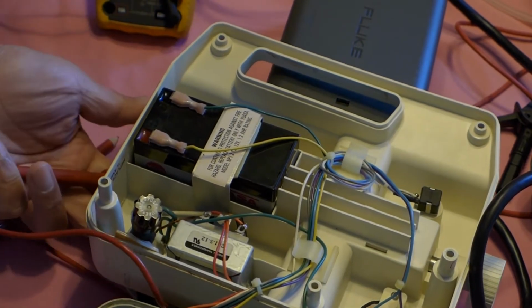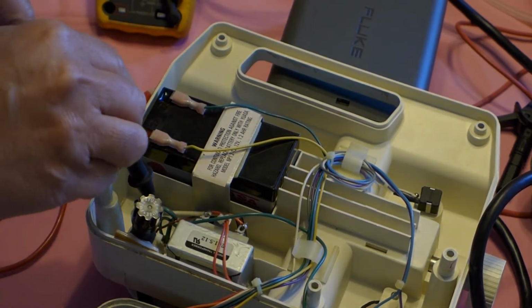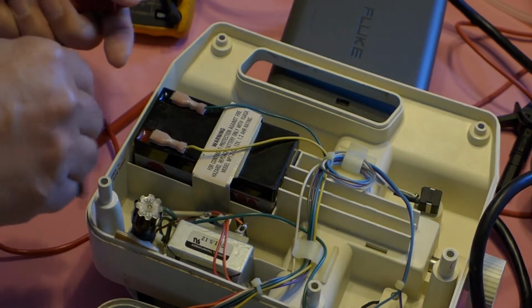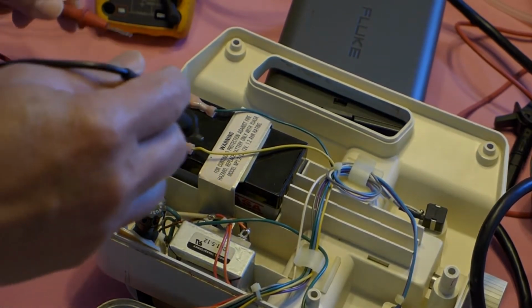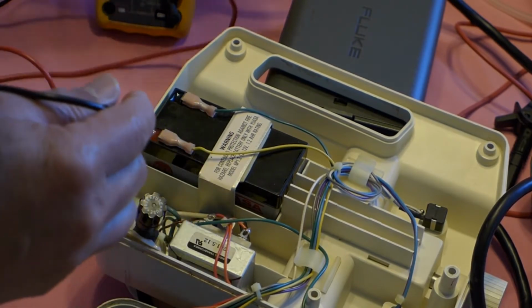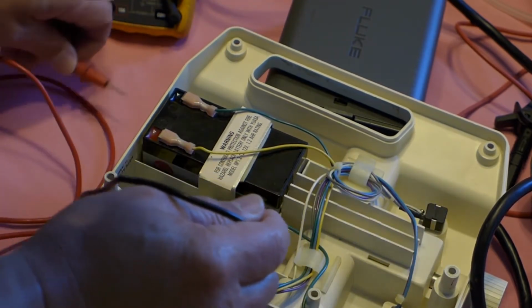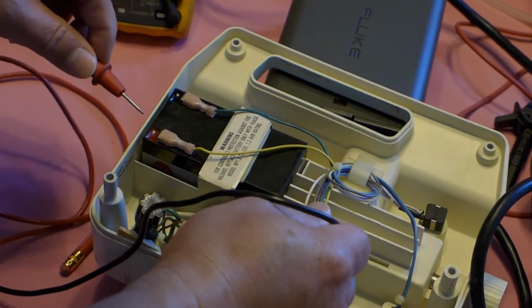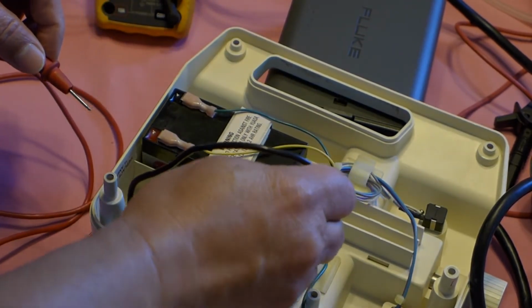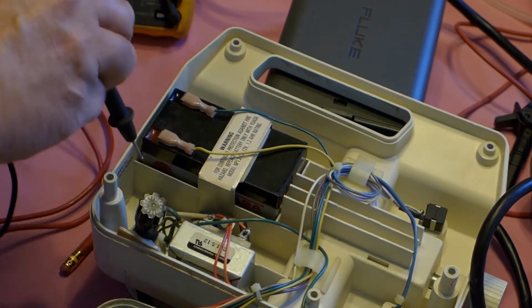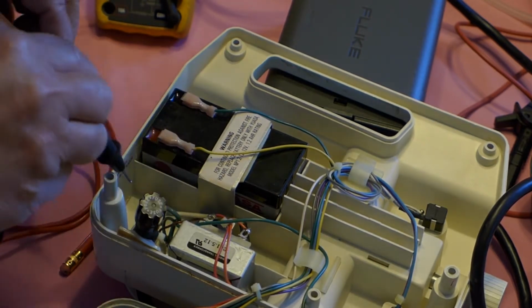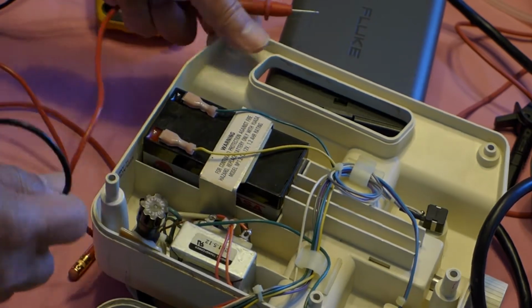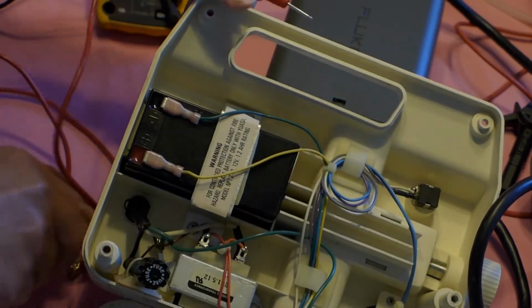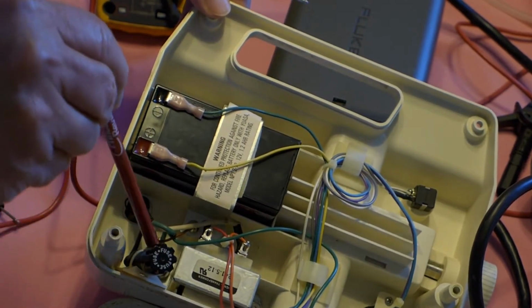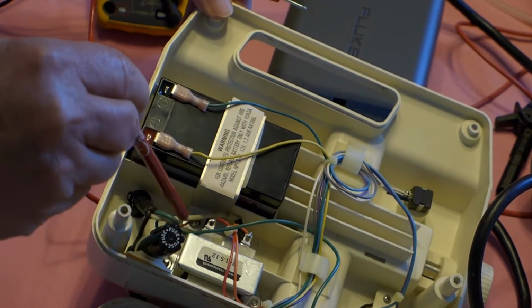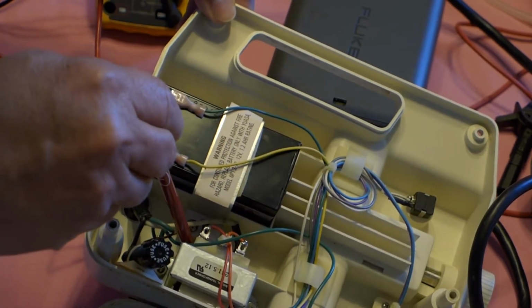So in the back, when you flip that, you need to check the leakage. That is where the ground port is going to be, from the other side of the cover. Now when you look at the white one on this side, you're going to see the white one come to one side of the transformer, at the bottom of the transformer. And then the black wire comes over here and connects to the fuse. Then from the fuse it goes to the other side of the transformer.